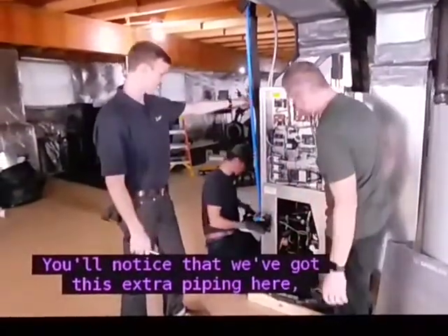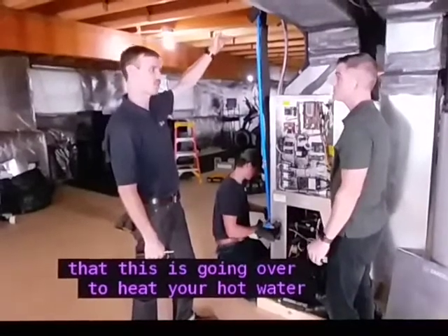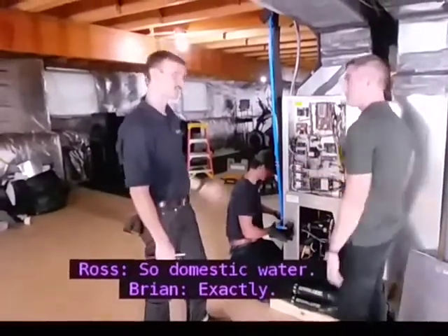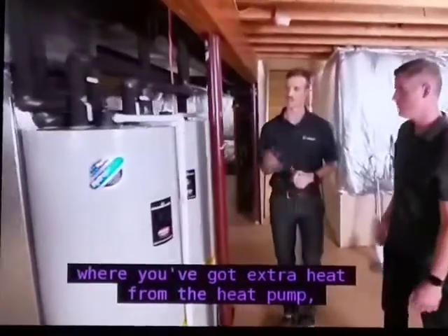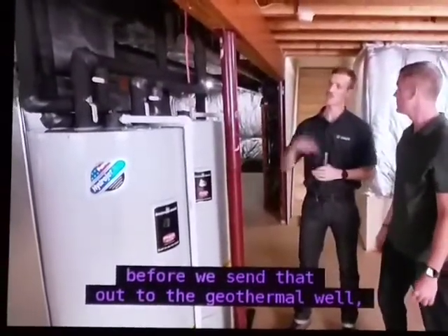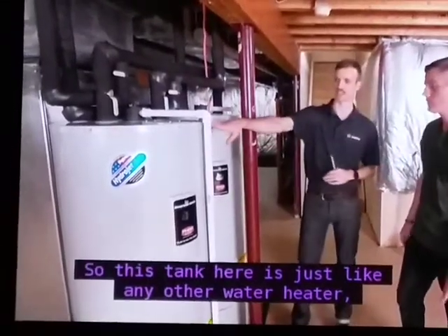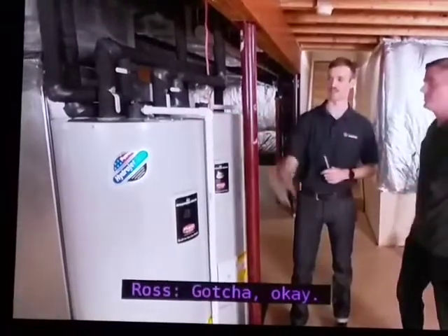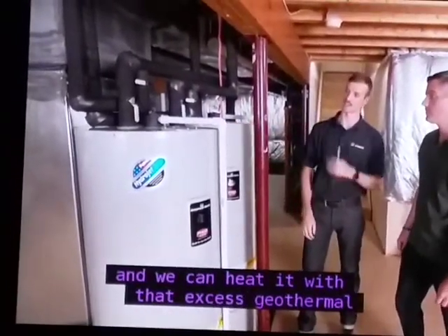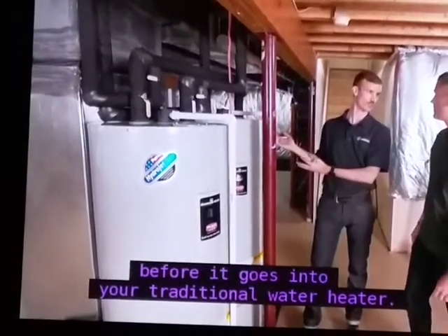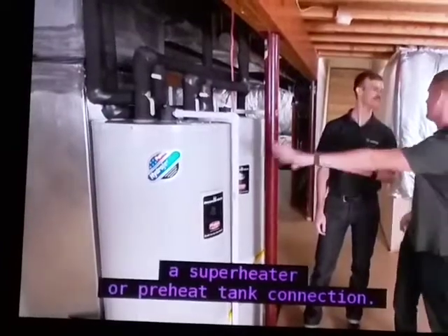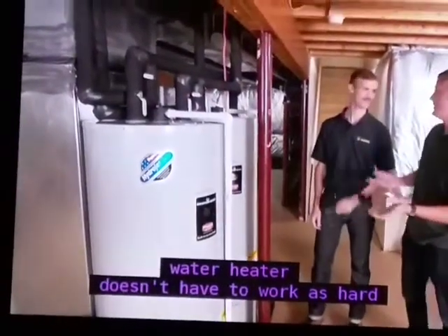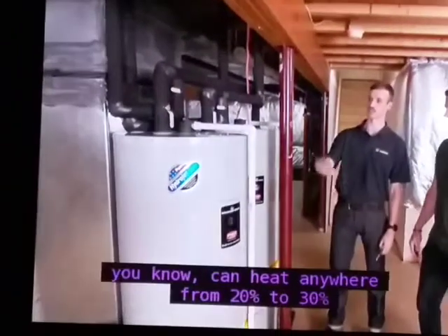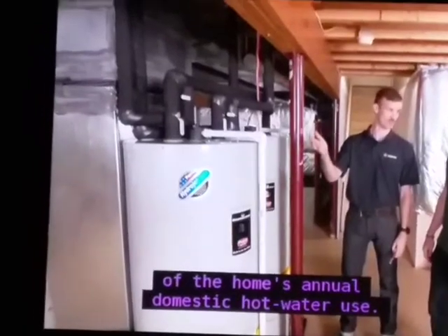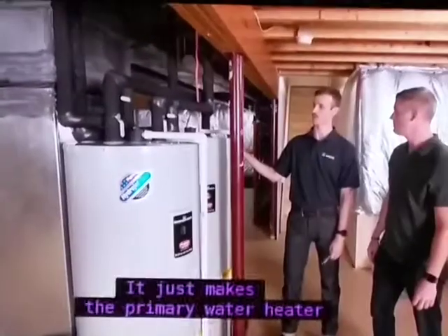What about the blue pipe? Yeah, you'll notice that we've got this extra piping here that is going over to heat your hot water for things like showers or dishwashing. So domestic water. Exactly. Okay. So in cases, for example, like the summertime where you've got extra heat from the heat pump, before we send that out to the geothermal well, we can send it into a preheat tank. This tank here is just like any other water heater, but we've just not connected it to any power, right? Gotcha. Okay. So the cold water comes in here and we can heat it with that excess geothermal heat before it goes into your traditional water heater. Got it. So it's commonly called the desuperheater or preheat tank connection. Exactly. And so your electric water heater doesn't have to work as hard because it's got preheated water. Exactly, and it can heat anywhere from 20 to 30% of the home's annual domestic hot water use. Okay. It just makes the primary water heater have to work a little less hard.